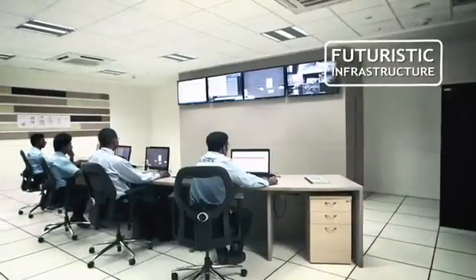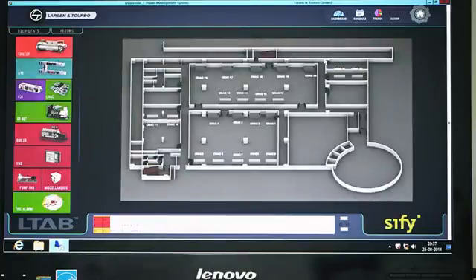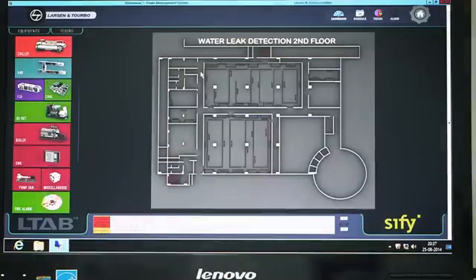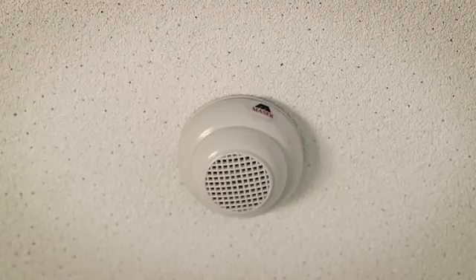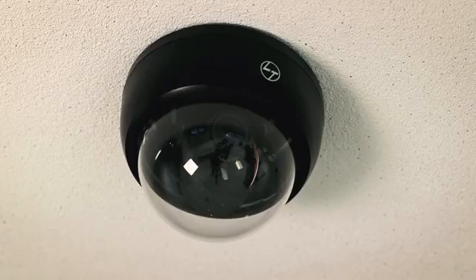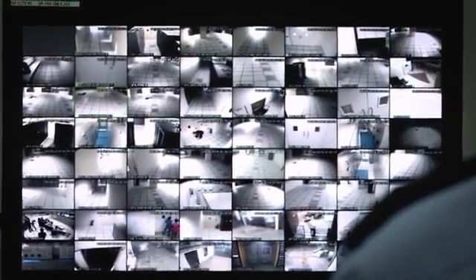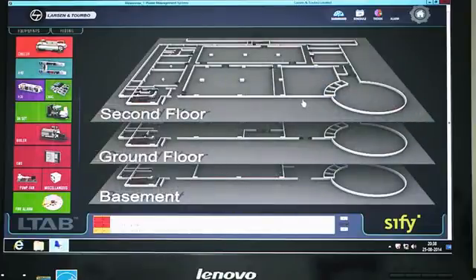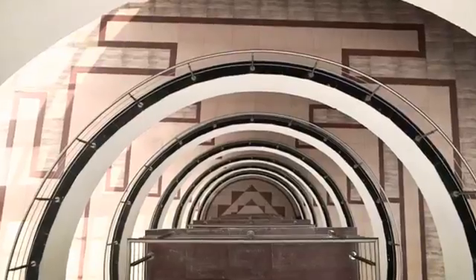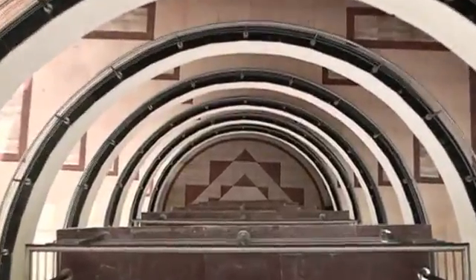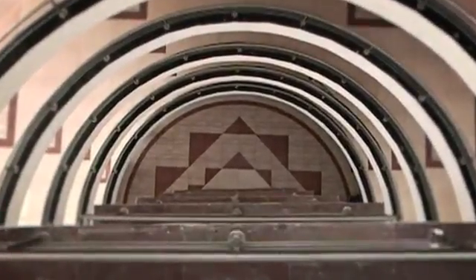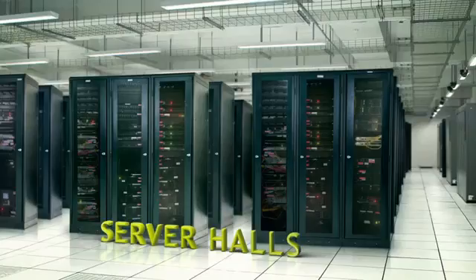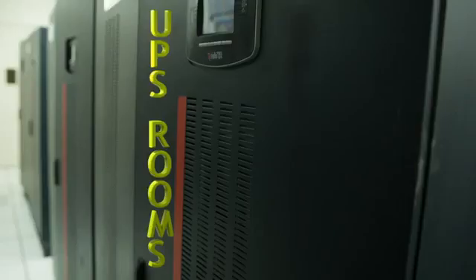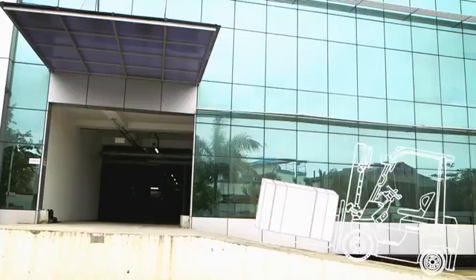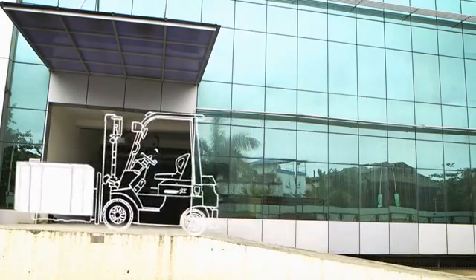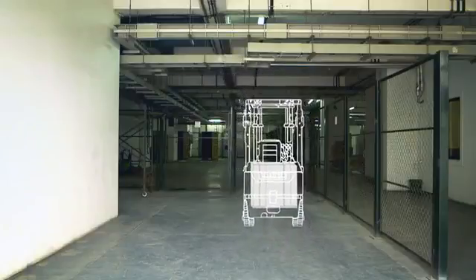A centralized console manages all components of the building management system, such as temperature, humidity, fire detection, smoke sensors, water leakage systems, and electronic rodent control. The safety features are further backed by surveillance cameras that cover all the critical areas of the Sify Cloud Center. The building management system raises alarm on any deviation in performance of these parameters. Sify Cloud Center is managed by separate specialized functional areas to ensure better operation and security control. Command center, server halls, electrical rooms, communication room, UPS rooms, battery rooms. A dedicated freight lift and loading dock at the facility provides smoother movement of materials like servers and storage devices.